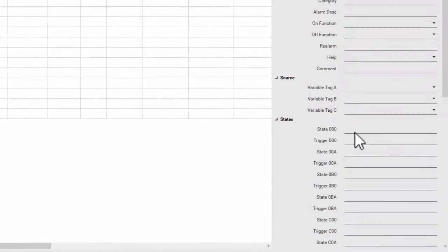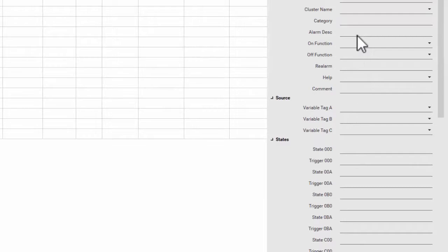The state field is the text that can be displayed when the alarm is active, though this is actually consumed by the description field above, and I must point you to the built-in help for details. If you want to trigger an alarm for this state, set the trigger field to 1 or leave it blank, or 0 otherwise. These alarms may be more useful in process control, for example, triggering a pump when certain valves are open, but they're uncommon in the electrical field.